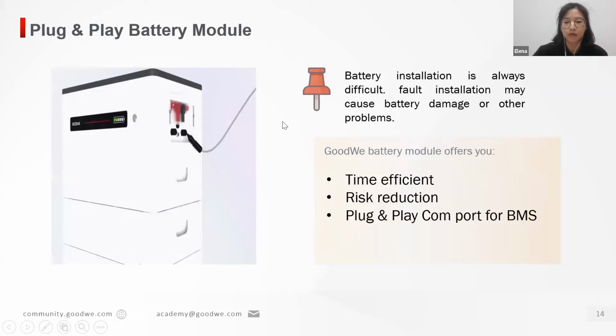But for the storage inverter, the system is more complex, so we need to install the batteries. And in fact, batteries used to be difficult to install. They should be connected without any mistake, otherwise it may cause battery damage or other problems. Therefore, GoodWe has put a lot of thought into the battery product design. We will offer you a time-efficient, risk-reducing plug-and-play COM port for BMS connection.